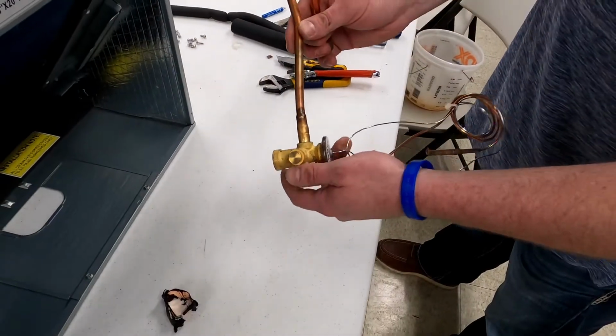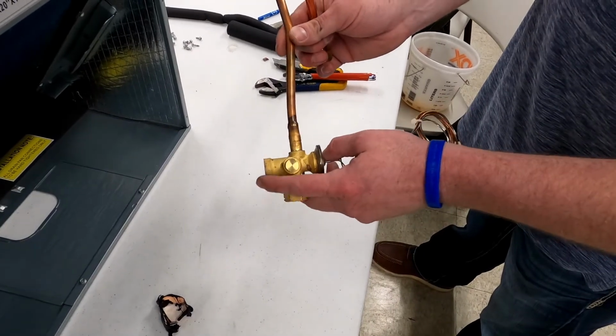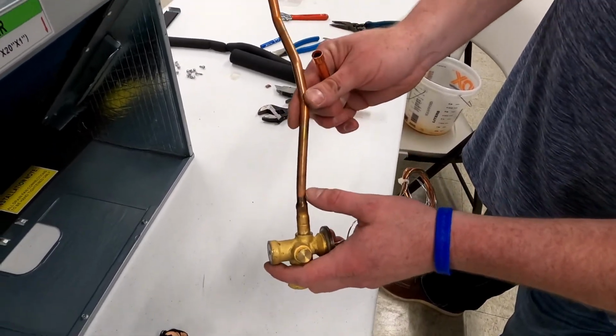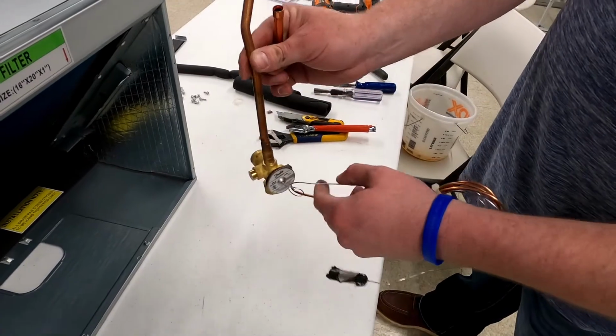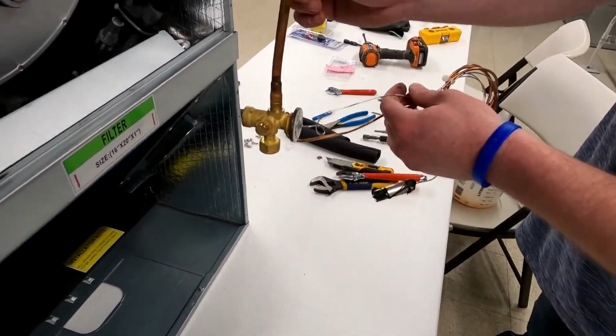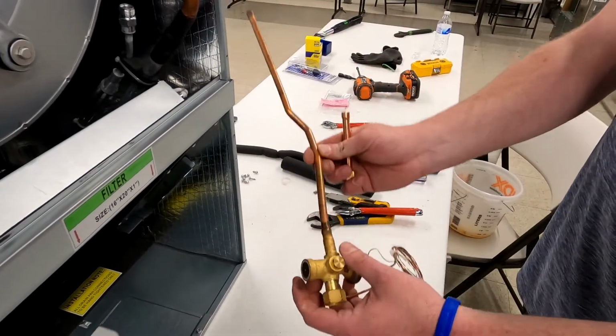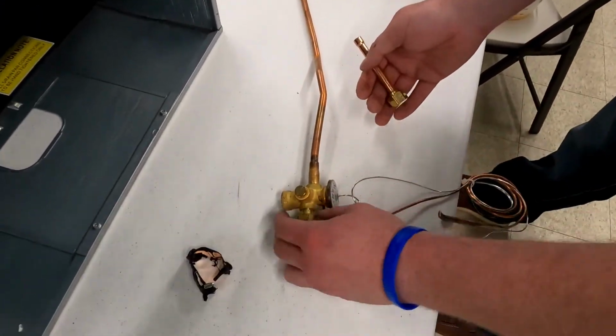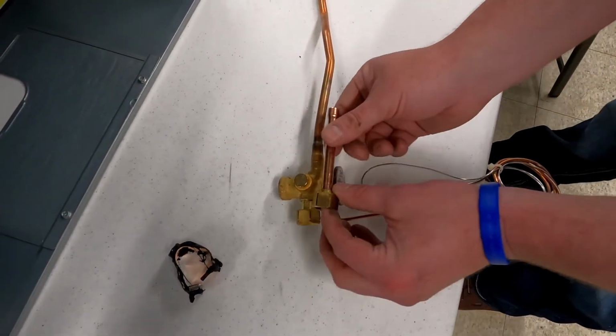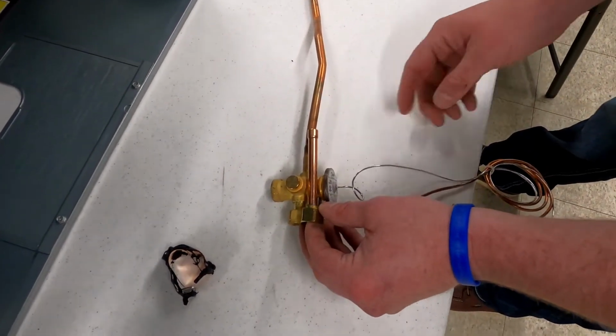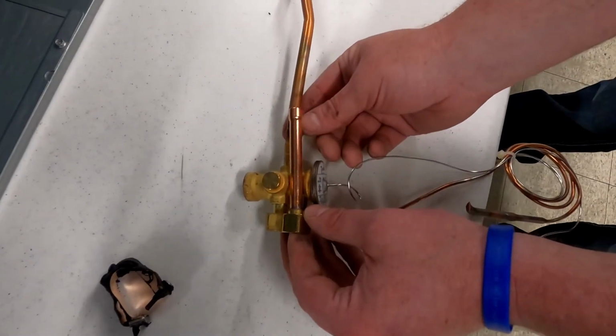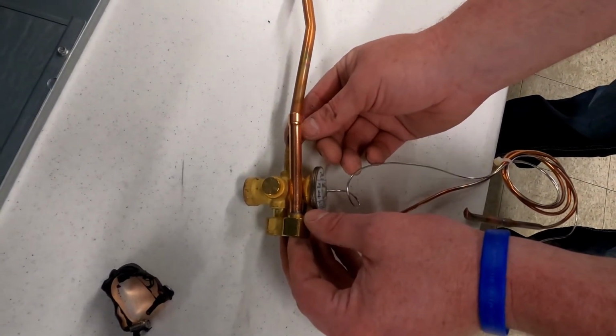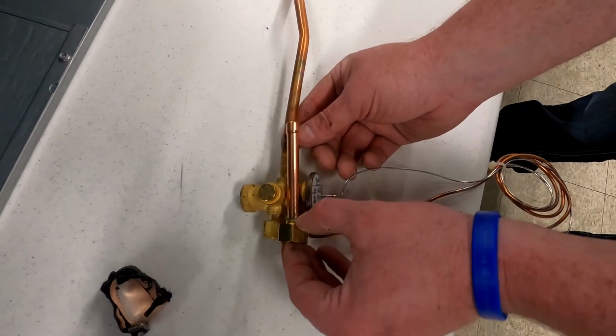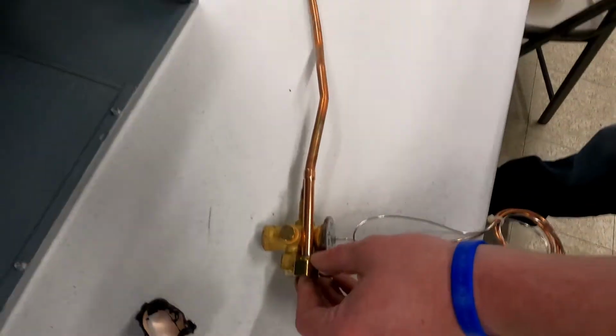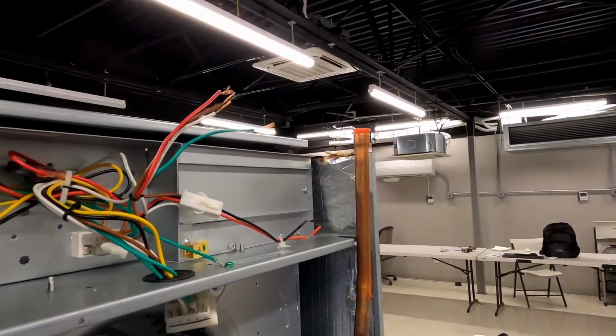The pipe adapter comes with a brand new seal, which will give you no chances of having a leak. So the section of pipe that we removed from inside the unit that's brazed to the TXV is specially bent to make it out of the unit on the right angle. So you'll want to reuse that pipe after you remove it. What you want to do is take the adapter fitting and mark your cut and cut this off there to remove the expansion valve. Now you can reuse that pipe and it's going to exit the unit at the same spot.